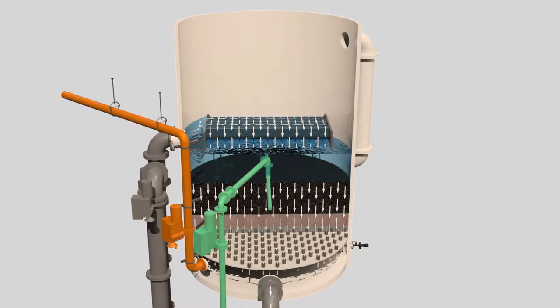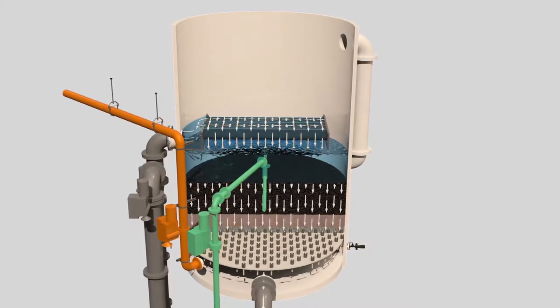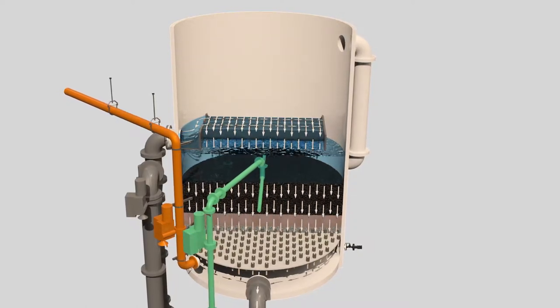To lower the pH, sulfuric acid is added upstream of the media filters, which helps prevent mineral scaling or plugging of the filter media.